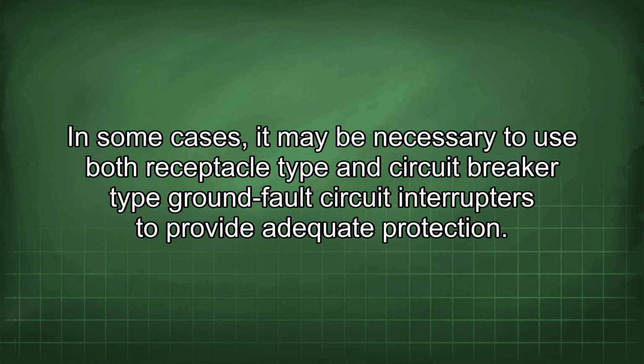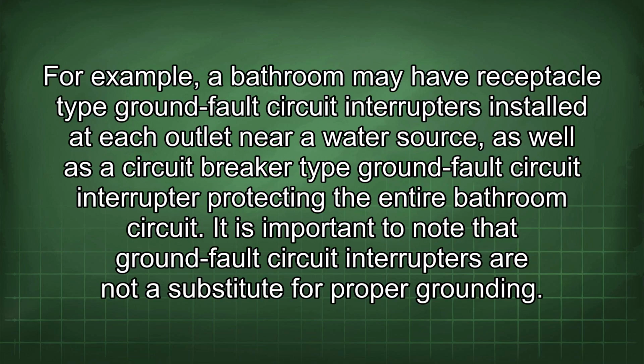In some cases, it may be necessary to use both receptacle type and circuit breaker type ground fault circuit interrupters to provide adequate protection. For example, a bathroom may have receptacle-type ground fault circuit interrupters installed at each outlet near a water source, as well as a circuit breaker-type ground fault circuit interrupter protecting the entire bathroom circuit.